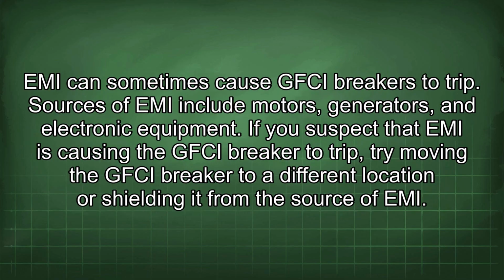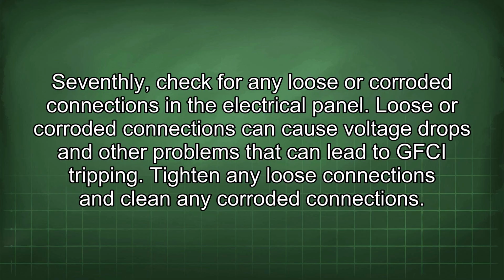EMI can sometimes cause GFCI breakers to trip. Sources of EMI include motors, generators, and electronic equipment. If you suspect that EMI is causing the GFCI breaker to trip, try moving the GFCI breaker to a different location or shielding it from the source of EMI. Seventhly, check for any loose or corroded connections in the electrical panel. Loose or corroded connections can cause voltage drops and other problems that can lead to GFCI tripping. Tighten any loose connections and clean any corroded connections.